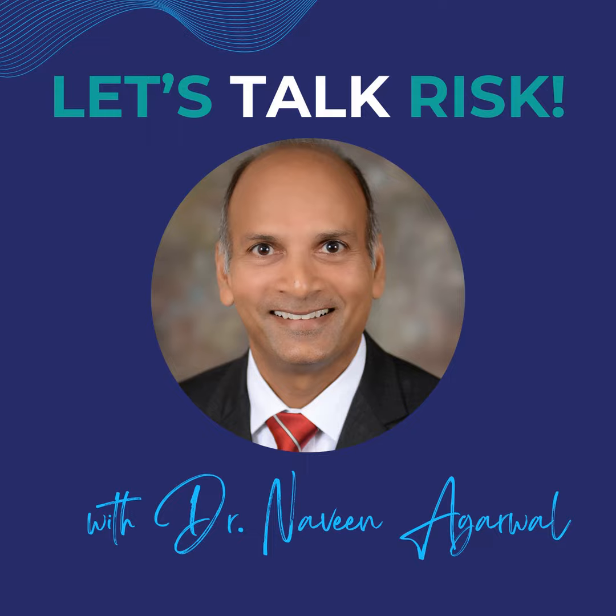Usually where I see that is when the company themselves will identify training as a mitigation, and identify whether it's required or not. So where that comes in is if you're identifying training is helpful, but you're not going to require it, and people may do it or may not do it, in that case, when you come to human factors evaluations, you need to evaluate it potentially without training, right? If you're not going to make sure that's going to happen.